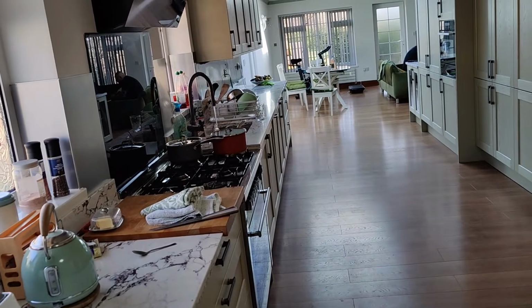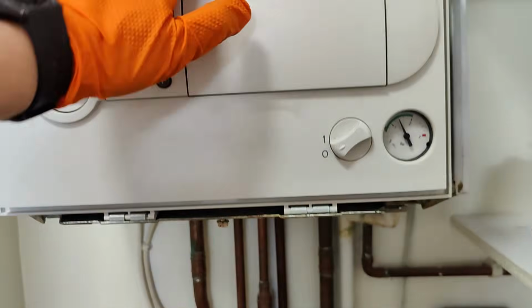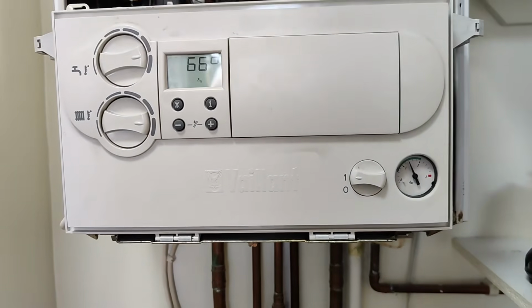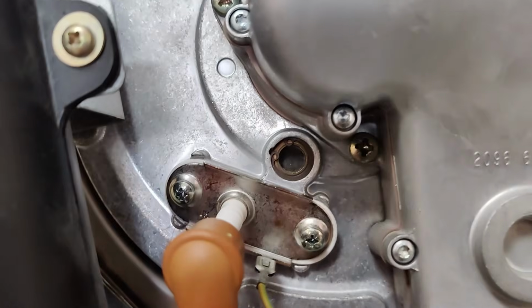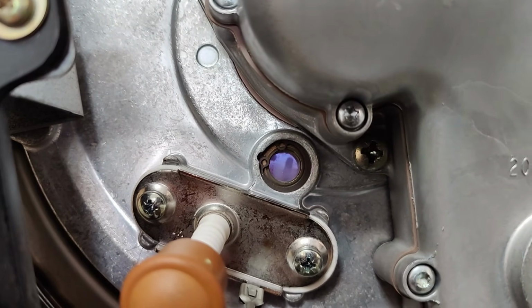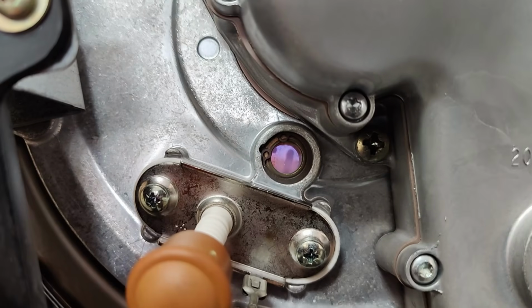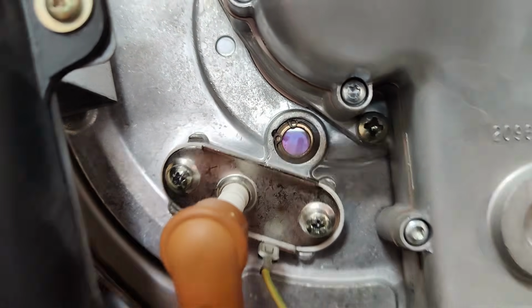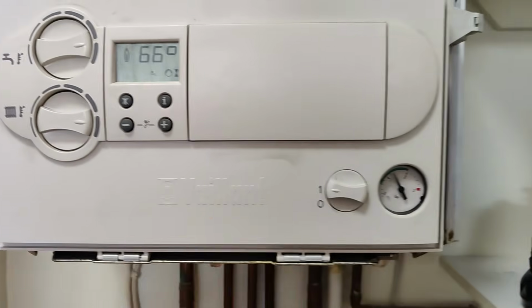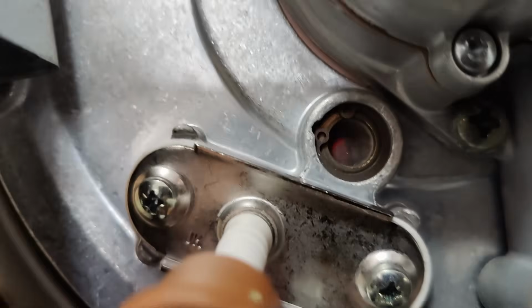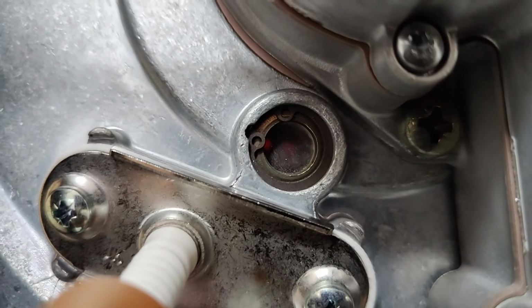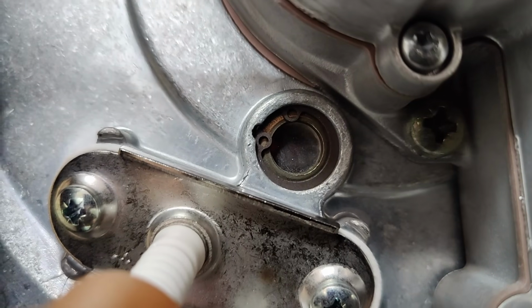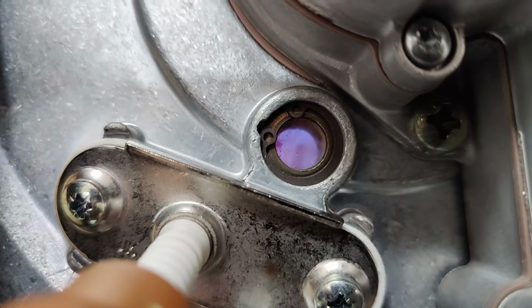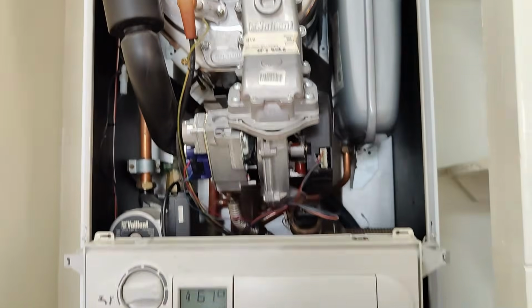So the old valve's out, new gas valve's in. We have the demand on hot water there. Let's turn the boiler on, let's see what it does. Absolutely fine first time. So as you can see, it's starting to work perfectly fine now. It's not giving us that trouble anymore. Let's just try once more just to be on the safe side before I do all the relevant analyzer testing. There you have it. So yeah, it was definitely the gas valve that was faulty on this one.